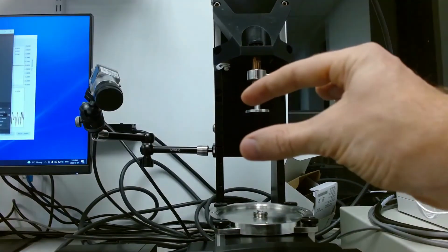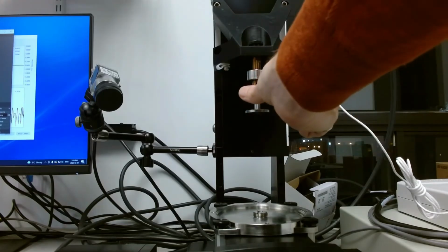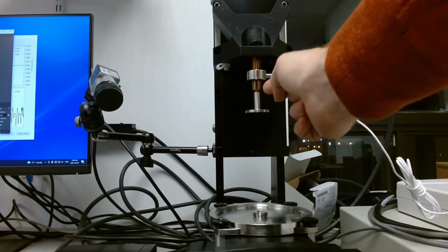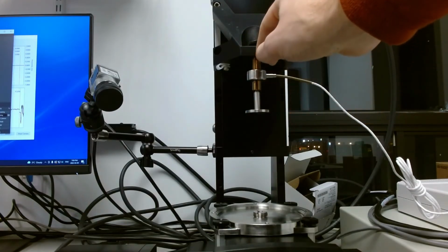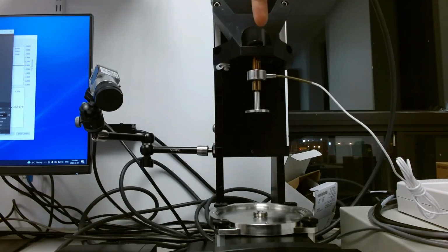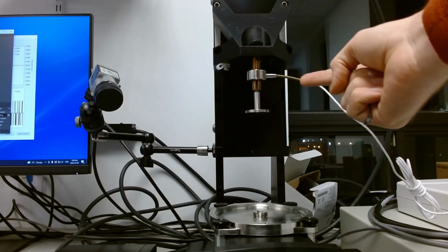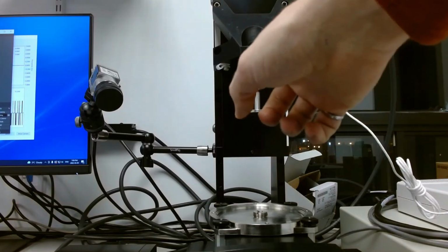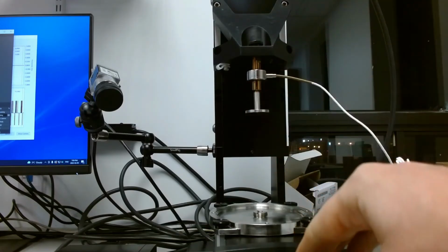The reason I only use 2 fingers is because I want to minimize the amount of torsion that's applied to this load cell. This one in particular is a single axis load cell, and it's only meant to be loaded in the vertical direction. So any loads from the side, front, or torsional have a risk of breaking this load cell.